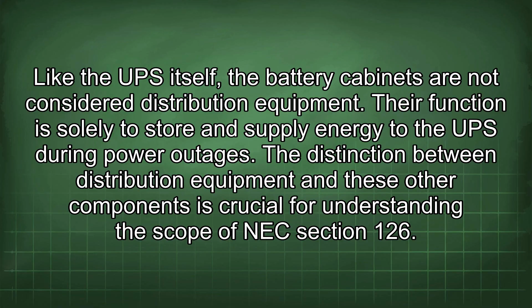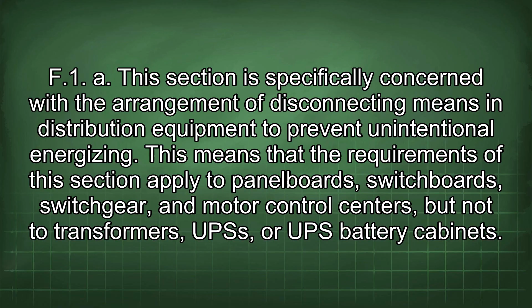The distinction between distribution equipment and these other components is crucial for understanding the scope of NEC Section 126.F.1.a. This section is specifically concerned with the arrangement of disconnecting means in distribution equipment to prevent unintentional energizing. This means that the requirements of this section apply to panel boards, switchboards, switchgear, and motor control centers, but not to transformers, UPSs, or UPS battery cabinets. To further clarify this distinction, let's consider some practical examples.